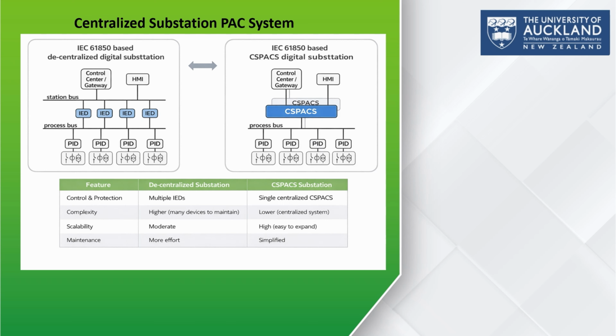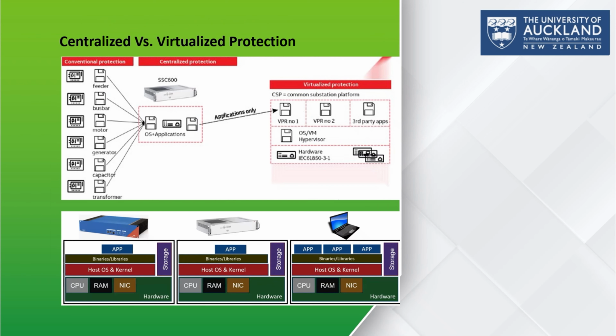Now, centralized versus virtualized protection. This image shows how substation protection has evolved from hardware-based devices to software-based virtual systems. In conventional protection, each feeder, transformer, generator, or motor has its own dedicated protection relay, meaning many separate devices, wiring, and hardware components. Centralized protection replaces these multiple relays with one central unit that runs several protection applications on a single piece of hardware, reducing equipment and simplifying maintenance, right?